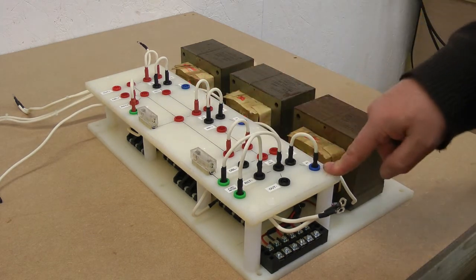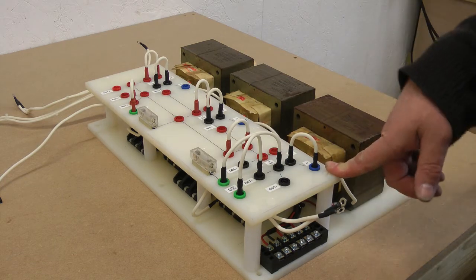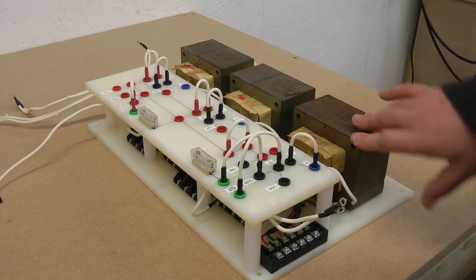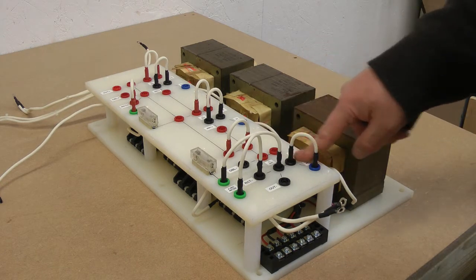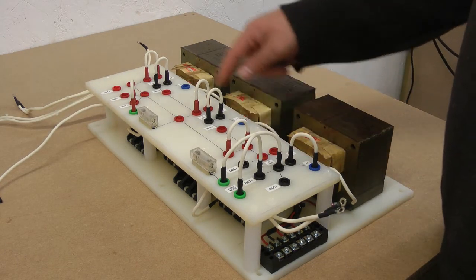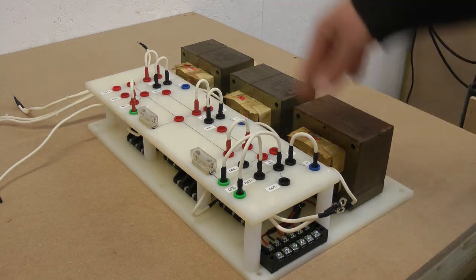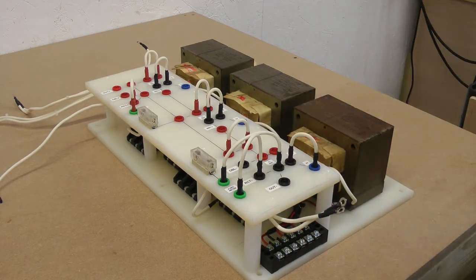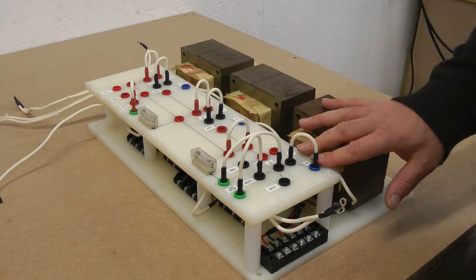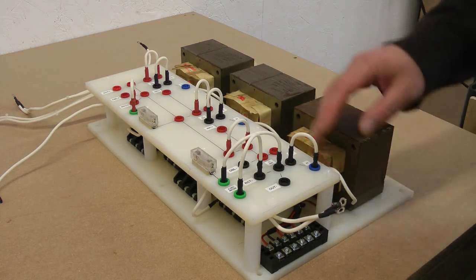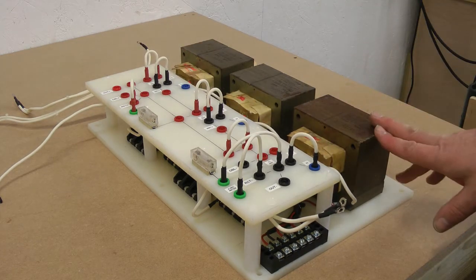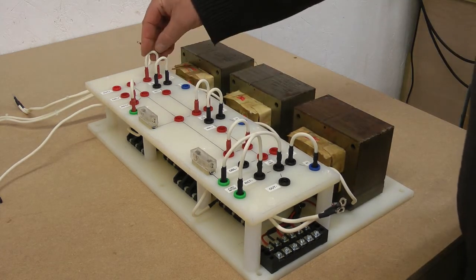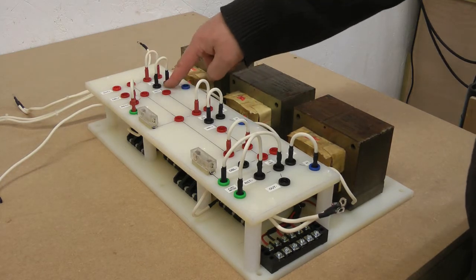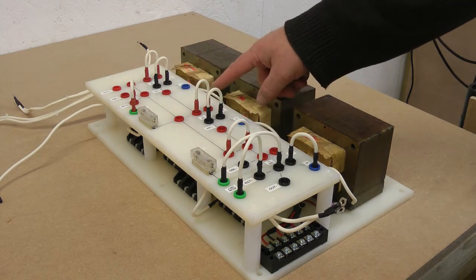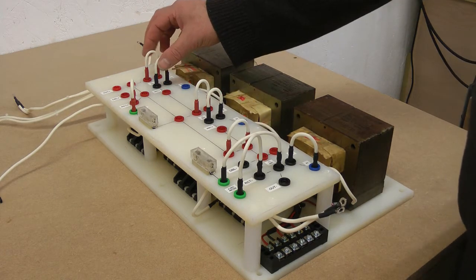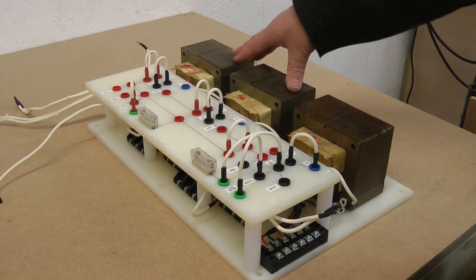So this forms a common rail, the blue. If I wanted to connect all 3 of these transformers in parallel, I would simply connect T1 to E1, T2 to E2, T3 to E3. I'll go through this matrix of connections on the right so you can see how it all works. That would put them all in parallel. In this case, this board is set up just for using 1 transformer. The other 2 aren't doing anything at all. The black lines on here show where there are connections. So these jumpers are just stored for these 2 transformers.